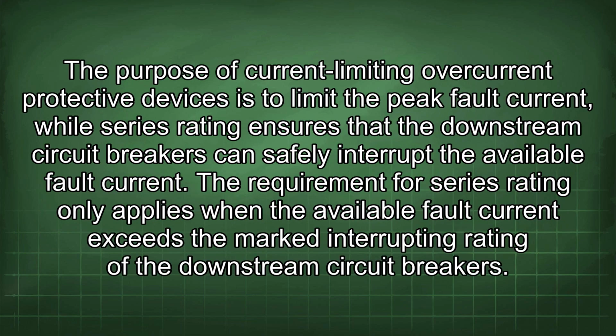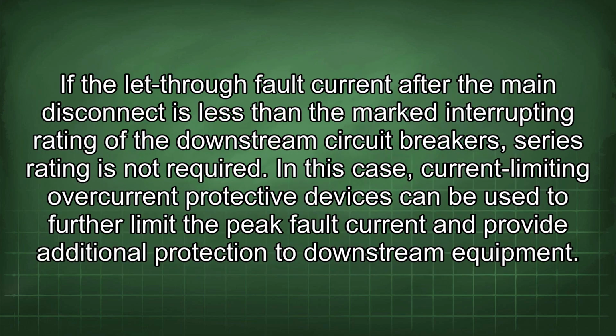The purpose of current-limiting overcurrent protective devices is to limit the peak fault current, while series rating ensures that the downstream circuit breakers can safely interrupt the available fault current. The requirement for series rating only applies when the available fault current exceeds the marked interrupting rating of the downstream circuit breakers. If the let-through fault current after the main disconnect is less than the marked interrupting rating of the downstream circuit breakers, series rating is not required.